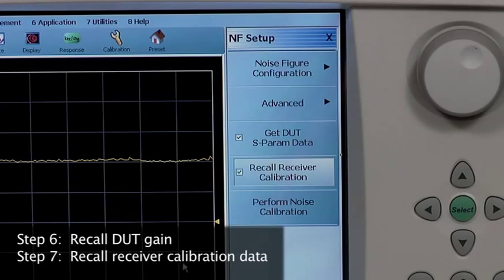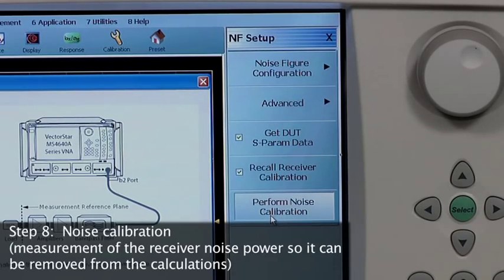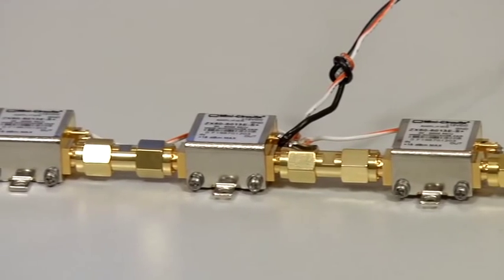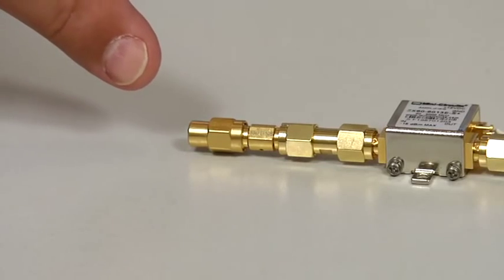We then perform step eight, the noise calibration, to calculate the receiver noise power so it can be removed from the calculations. Again, the Anritsu VectorStar cold source noise figure measurement methodology enables us to use a simple termination as the noise source.